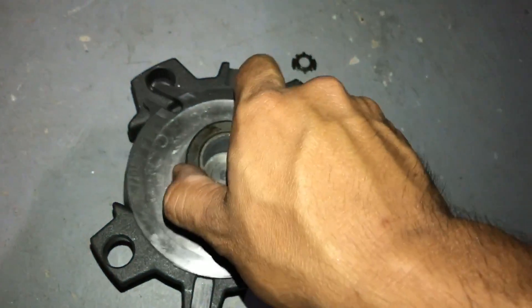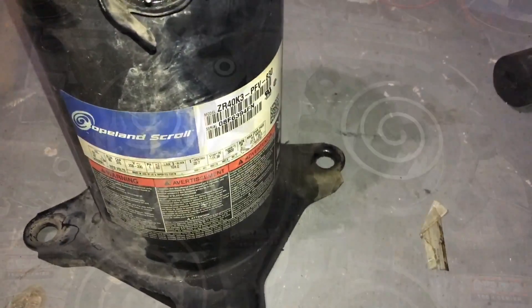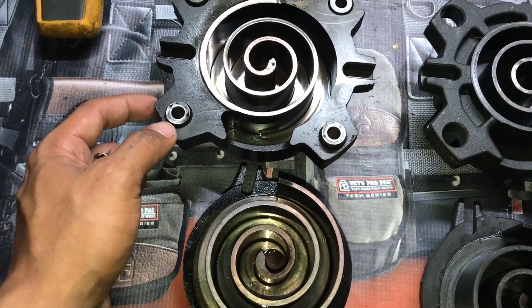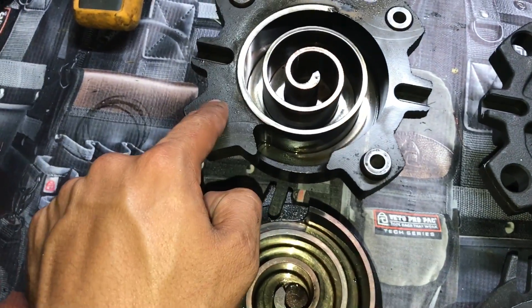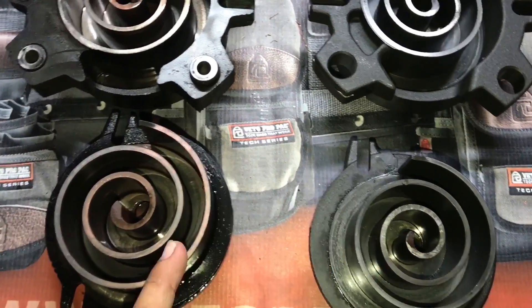Put them right next to each other and see the difference. I'll get this one opened and we'll see the size difference. This is a ZR40, an R22-407C compressor. This is a ZP42. It's 40,000 BTUs, and this one's rated at 42,000 BTUs. When you look at them, they look like they're the same size — physical dimensions.